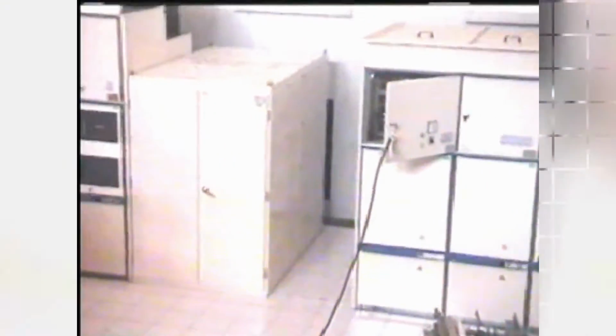Indoor switchgear consists of 6.6 kilovolt switchgear, 20 kilovolt switchgear, and low voltage switchgear. All switchgears are designed for a frequency of 50 Hz. The 6.6 kilovolt switchgear is installed for the generator circuit and station service transformer circuit. The switchgear is of rigid frame, floor standing structure completely enclosed by sheet steel. The 20 kilovolt switchgear is installed for the secondary circuit of the main transformer, 20 kilovolt distribution lines and station service transformer circuits. The low voltage switchgear is installed for the secondary circuit of the 150 kilovolt-ampere station service transformer.